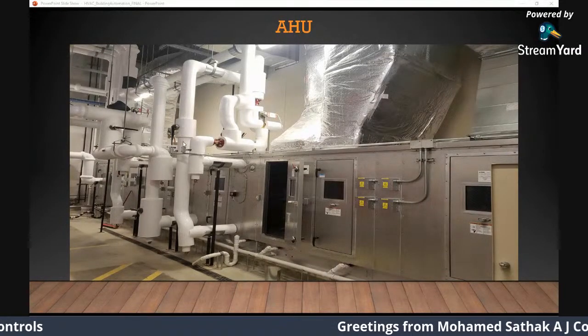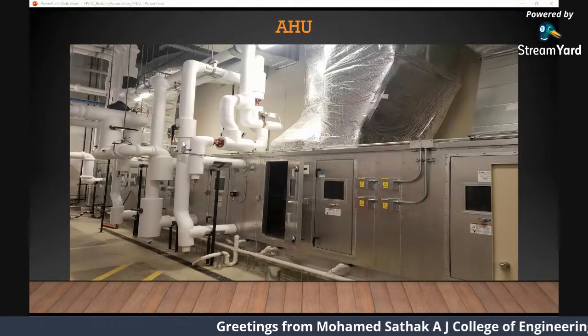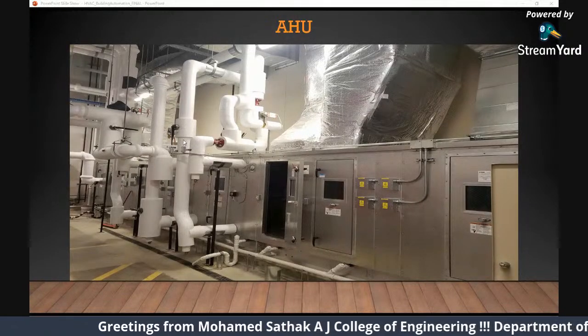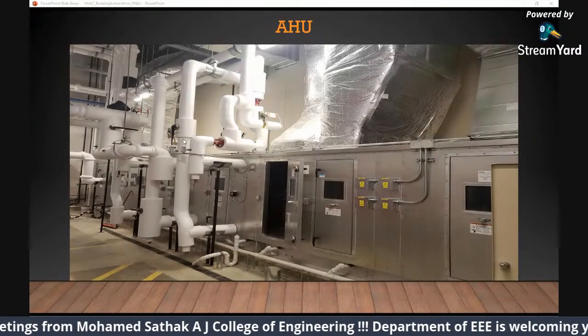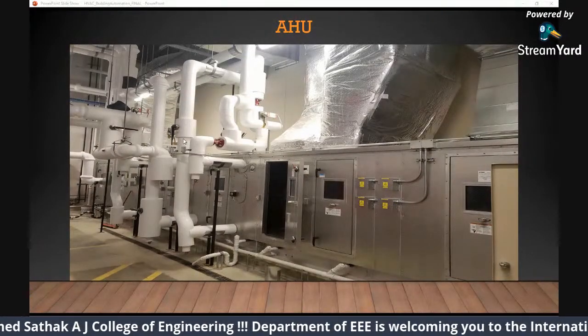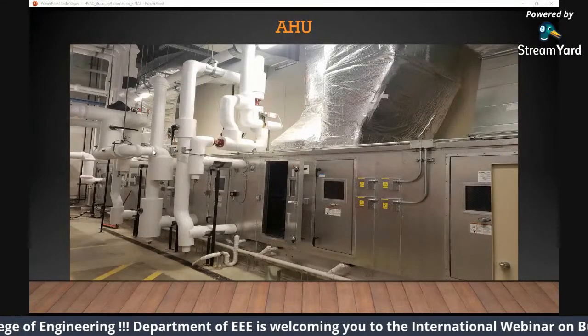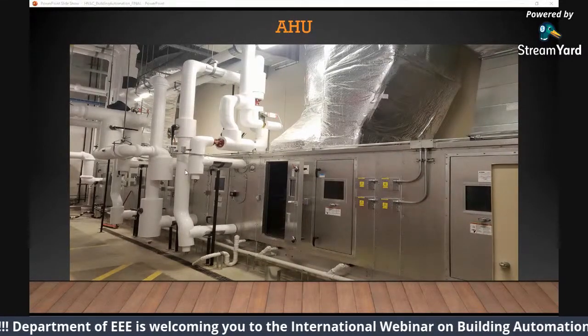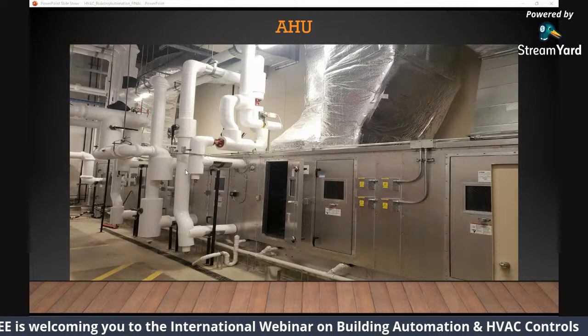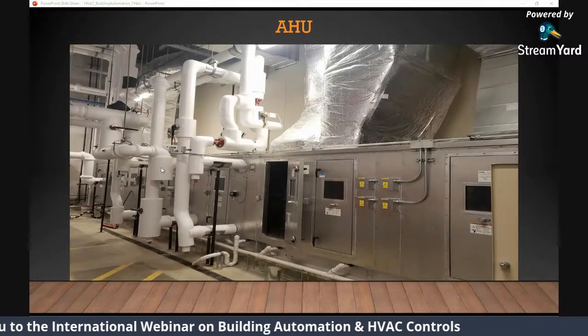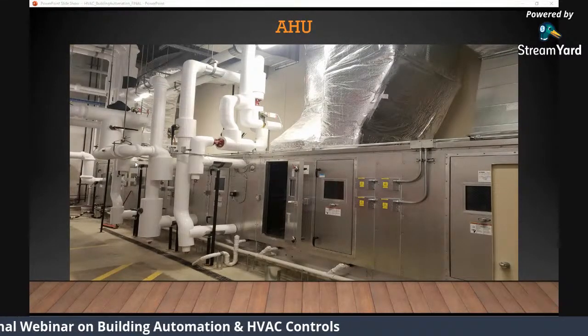If you see the white piping, it's your water pipeline coming from your hot water, I'm sorry, chillers and boilers. And yeah, we have something called a humidifier. I'm not getting into detail with that, but we'll just stick with chillers and boilers. So you have three pipes on your left, right? Starting from the first, the first one is your cold water from the chiller. The second one is your hot water from your boiler, and the third one is your humidifier.